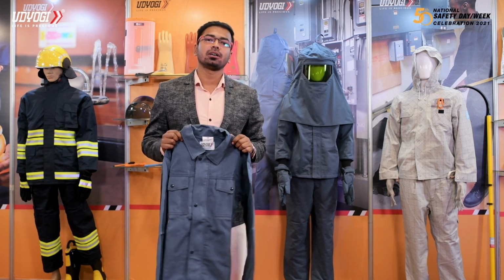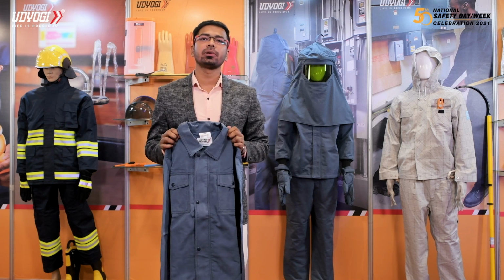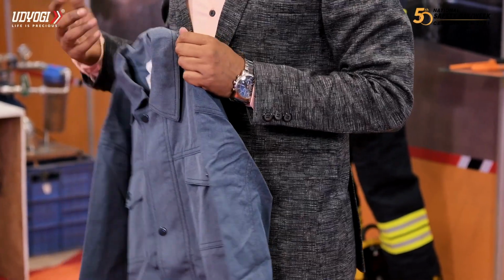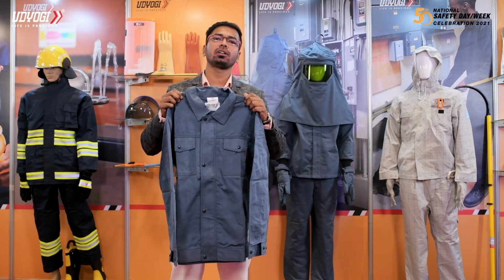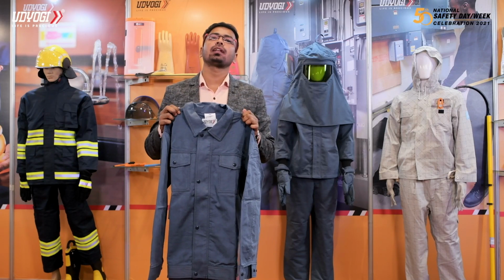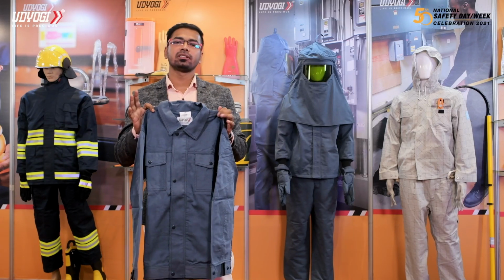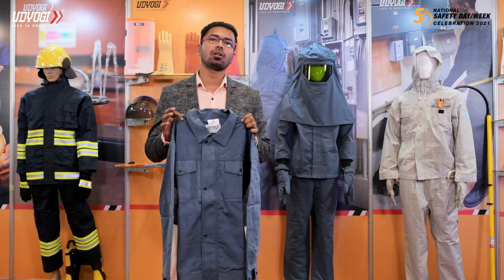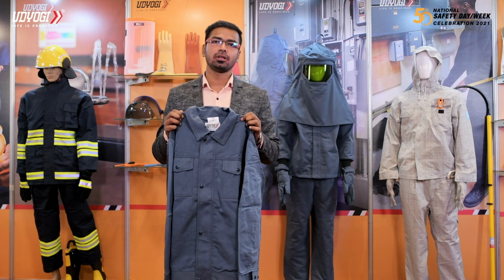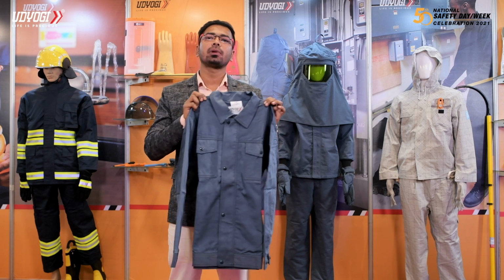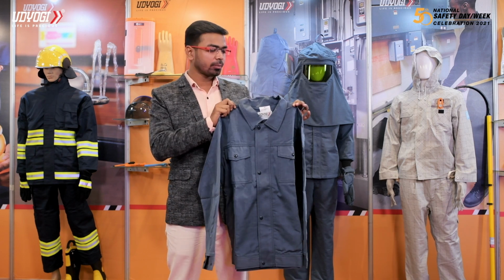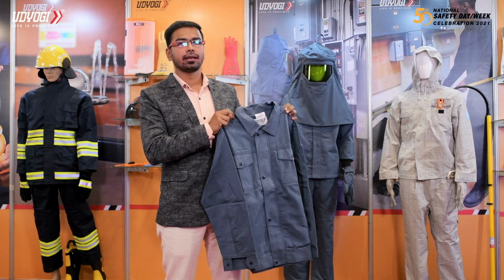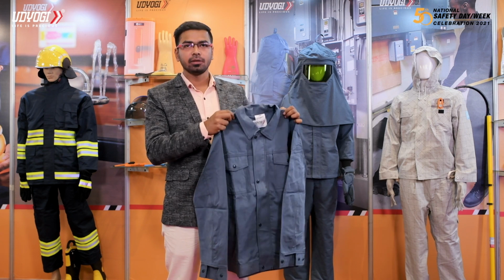In industries, there are common terms like 8 cal suit, 25 cal suit, 40 cal suit. But what is the meaning of this term cal? This is nothing but the ATPV or arc thermal performance value based on which we have to select our garments. The jacket you are watching now is an 8 cal jacket or ATPV rated 8 cal jacket.